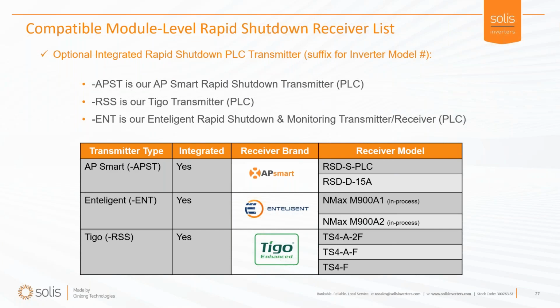We can install these transmitter boards for rapid shutdown, which is required after January 1st, 2019. If you're putting systems up on the roof, you want to make sure the firemen can come and shut these things down quickly and fight the fire the way they normally would. I know a lot of installers have worried about installing this extra equipment up on the roof to shut systems down quickly, but really it's about the firemen coming up to take care of any issues on your roof, using their standard firefighting methods so they can get the job done.